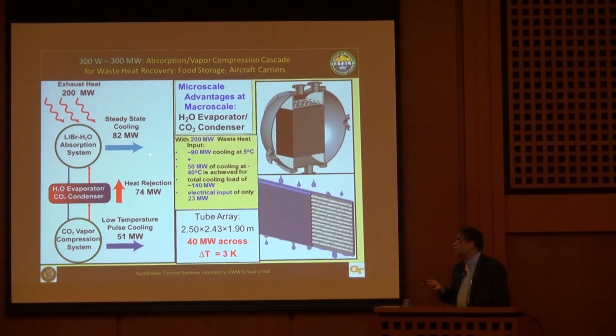So we took that waste heat and ran it through a lithium bromide water absorption system to provide cold water at approximately 5 Celsius, which can be used for cabin cooling on the ship. But if you also use that as the heat rejection coolant for a CO2 vapor compression system - this bottoming cycle - you put a little bit of electricity in it, and then you can get minus 40, minus 50 Celsius coolant that can cool high-powered electronics and so on.